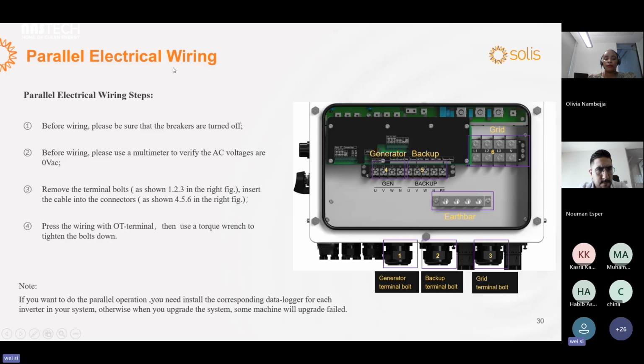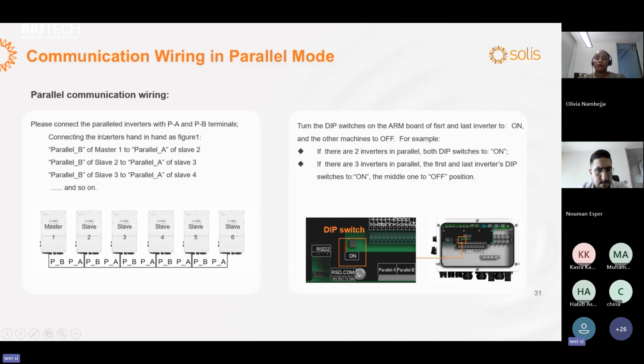About the parallel electrical wiring, just connect the cable from this terminal. Okay, about the communication wiring, you should connect the CAN cable like this: the first inverter PB port to the second PA port, then the PB of the second to this one, just like this diagram. After the communication cable is connected, you should turn the dip switch on the board of the first and the last inverter. For example, for this master inverter and the last one, you should turn the dip switch to the on position.